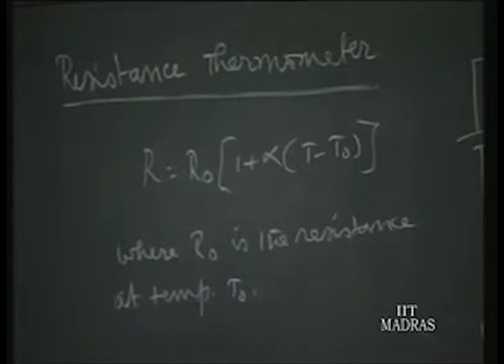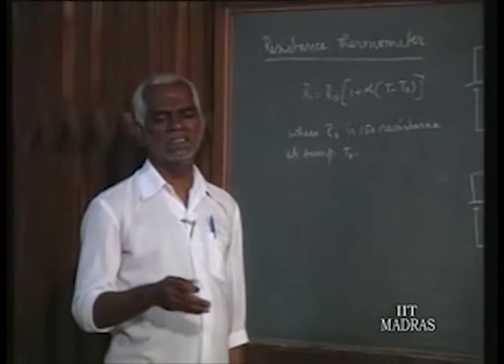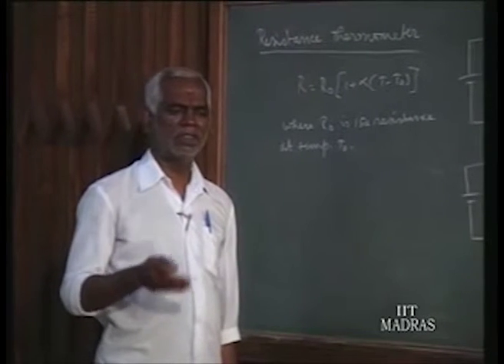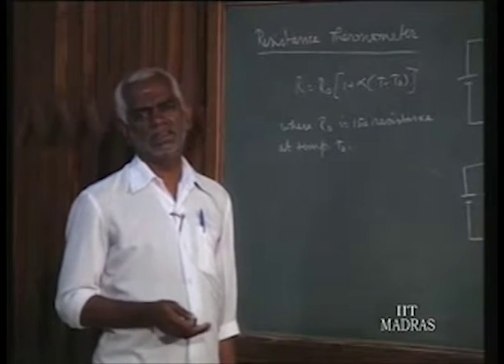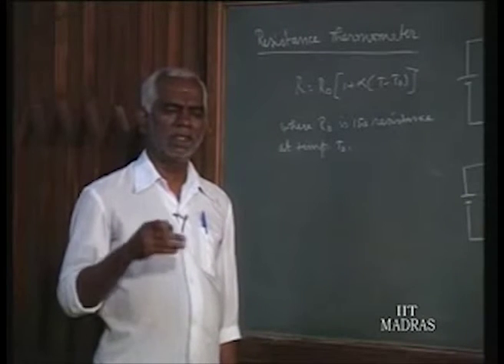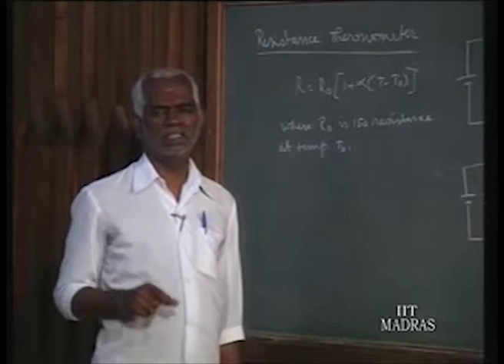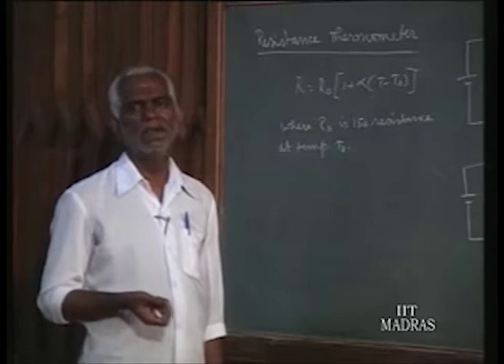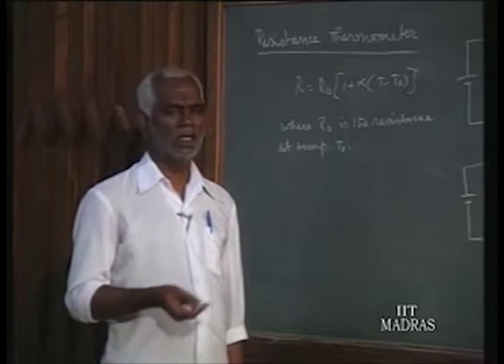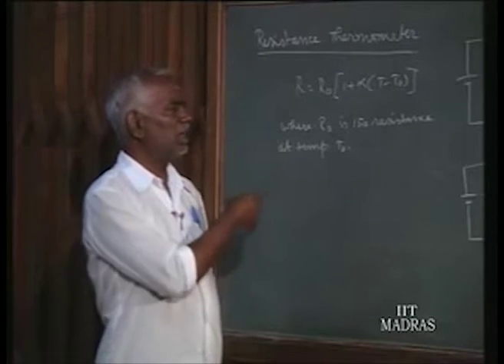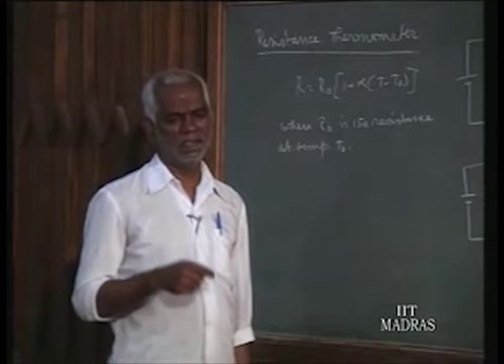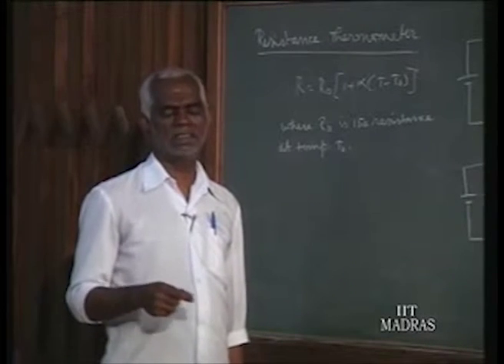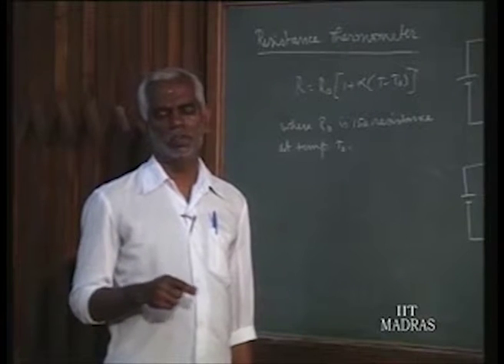This is the physical property that is made use of. When we subject a resistance to a temperature bath, its resistance changes. How to convert this resistance change into voltage change — this we have already learnt under strain gauge. When the strain gauge is pasted on any stressed member, the resistance is changed into voltage by using a Wheatstone bridge or AC bridge. Similarly here, the resistance element, the resistance of the thermometer, is connected as one of the arms of a 4-arm Wheatstone bridge.